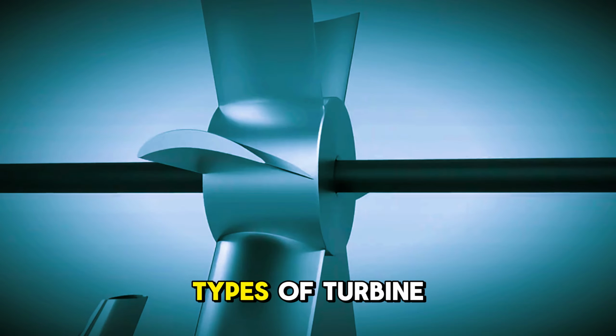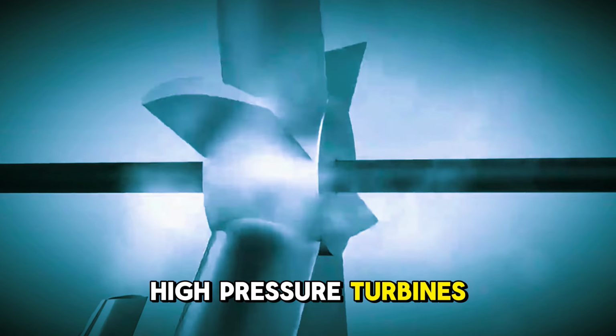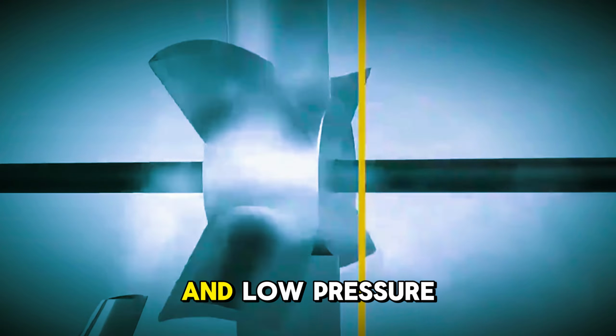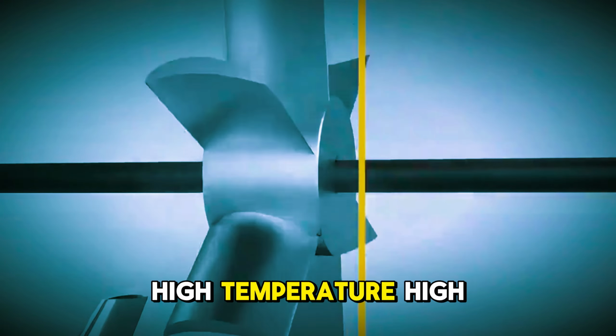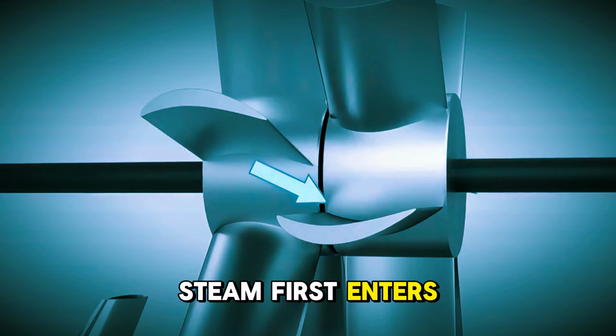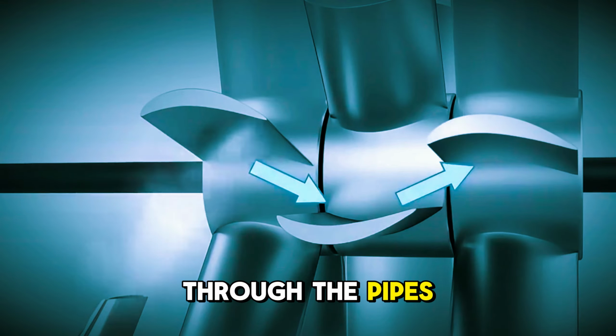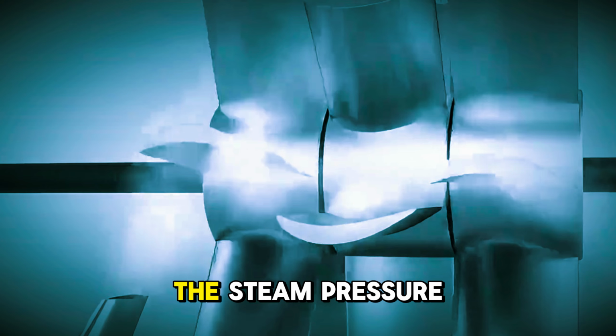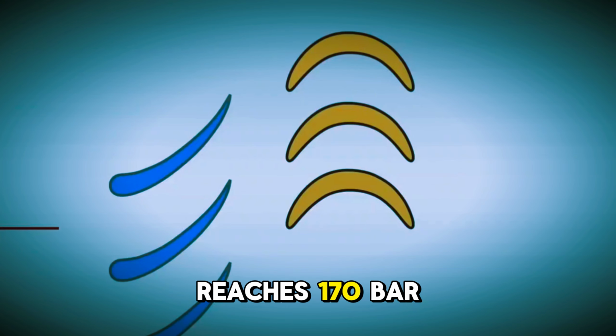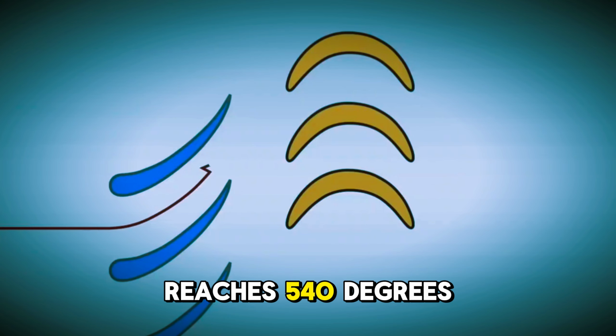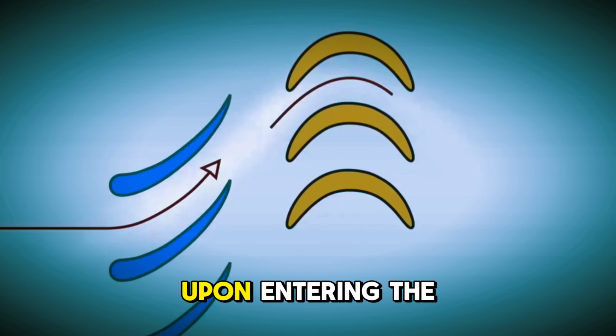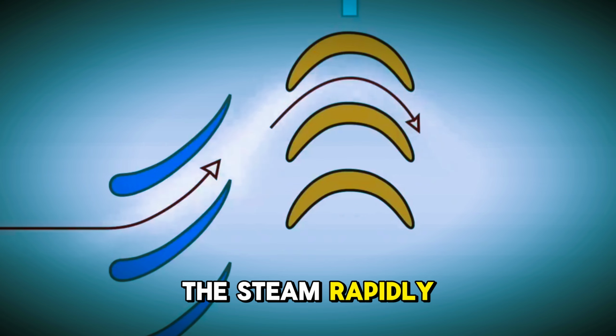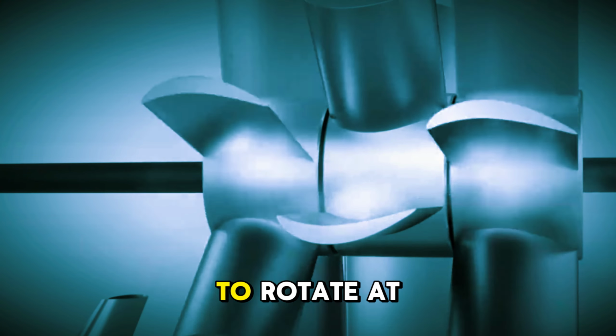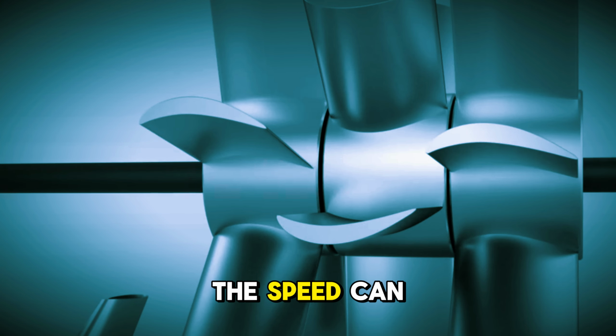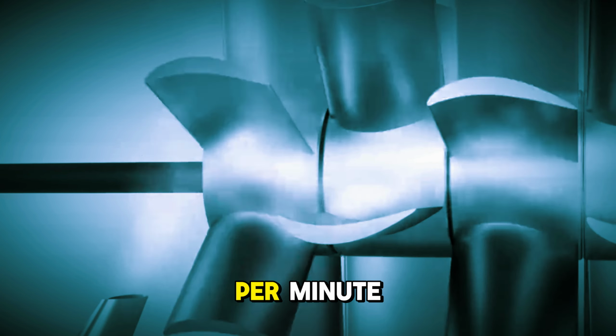There are three types of turbine units: high-pressure turbines, intermediate-pressure turbines, and low-pressure turbines. High-temperature, high-pressure steam first enters the high-pressure turbine through the pipes on its top. At this point, the steam pressure reaches 170 bar and the temperature reaches 540 degrees Celsius. Upon entering the turbine, the steam rapidly expands, causing the turbine to rotate at high speed. The speed can reach 3,000 revolutions per minute.